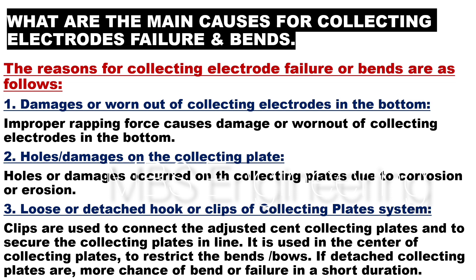One of the causes for collecting plates bends is damage or worn out of collecting electrodes in the bottom. Improper rapping force causes damage or worn out of collecting electrodes in the bottom. One of the causes for collecting plates bends is holes and damages on the collecting plate, which occur due to corrosion or erosion.